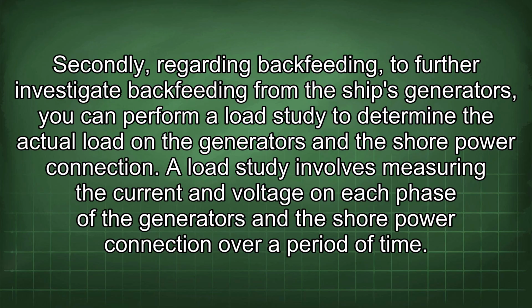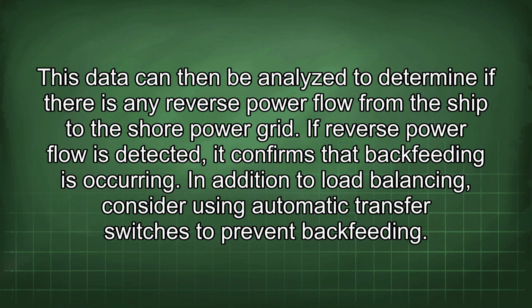Secondly, regarding backfeeding, to further investigate backfeeding from the ship's generators, you can perform a load study to determine the actual load on the generators and the shore power connection. A load study involves measuring the current and voltage on each phase of the generators and the shore power connection over a period of time. This data can then be analyzed to determine if there is any reverse power flow from the ship to the shore power grid. If reverse power flow is detected, it confirms that backfeeding is occurring.